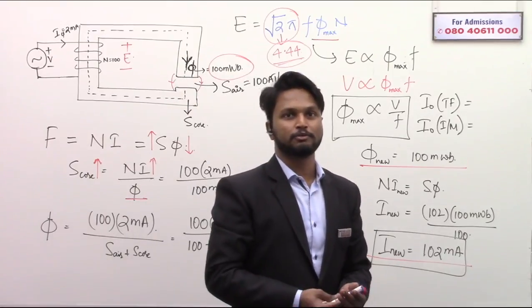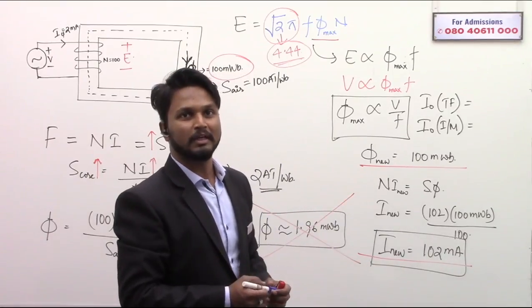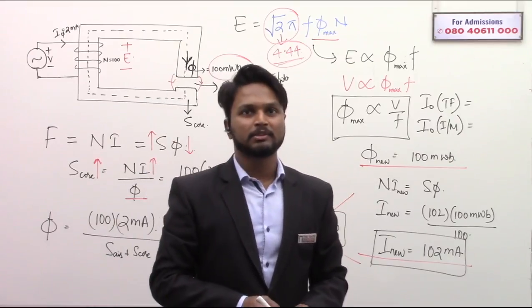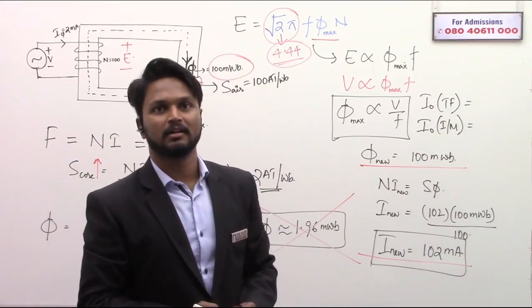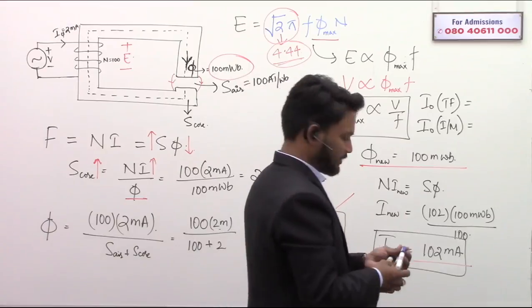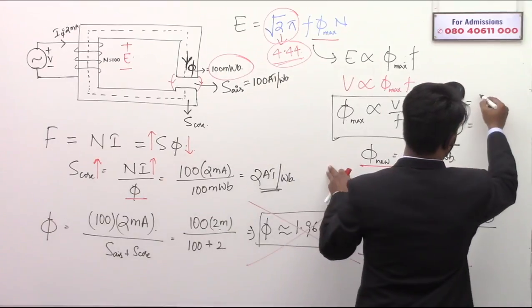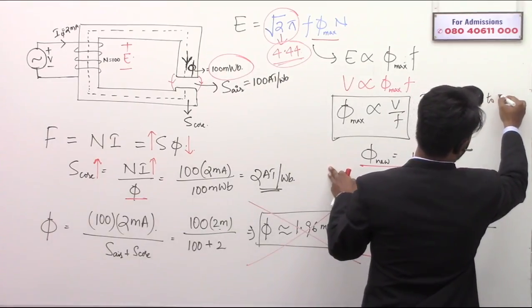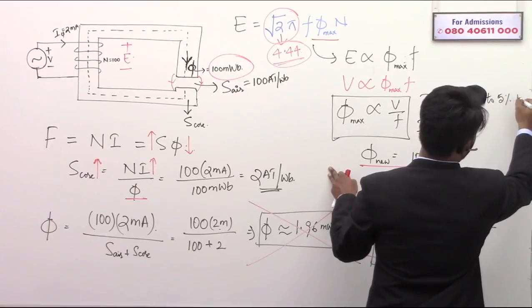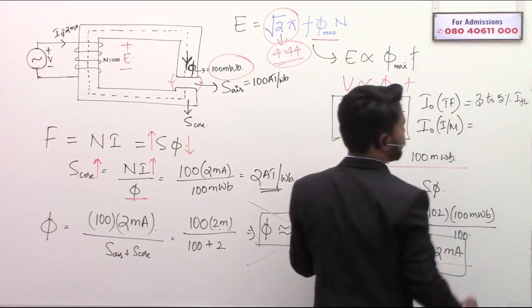Yes, very good - it is 5% of full load. It is not 5 to 8%, it is 3 to 5% of full load current, that is 3 to 5% of IFL, full load current.